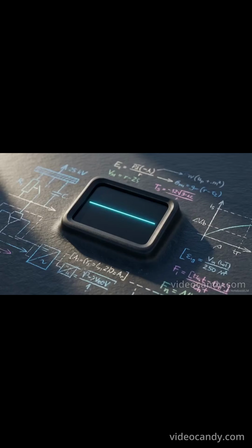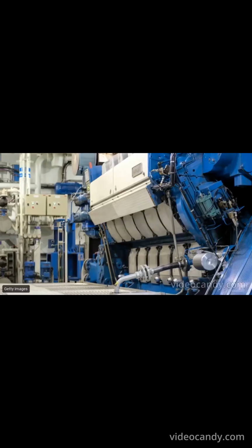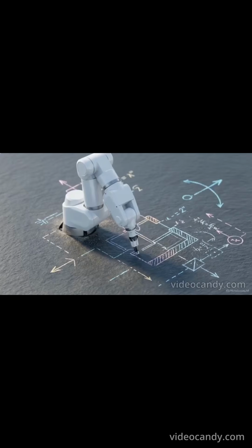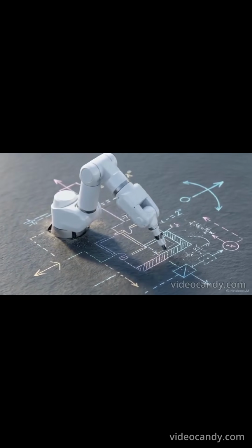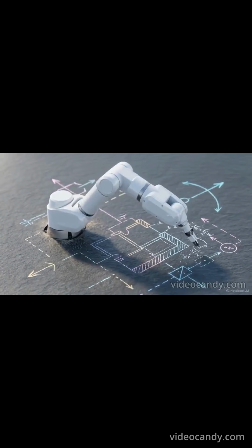Instead of inducing current in a cage, synchronous rotors use permanent magnets to physically lock into step with the stator's revolving field. Because these fields are locked, the motor achieves zero slip, turning at the exact speed dictated by the frequency of the grid. Induction motors dominate the world through rugged, slipping force, but achieving the absolute peak of digital control requires abandoning slip entirely for the rigid lock of synchronicity.